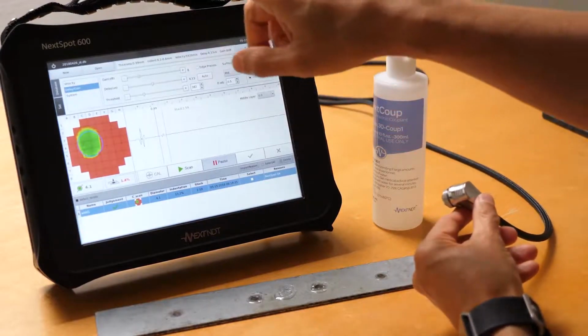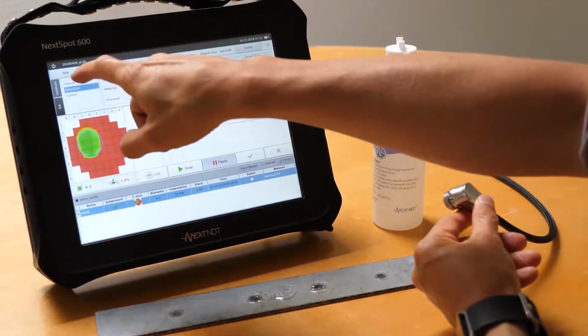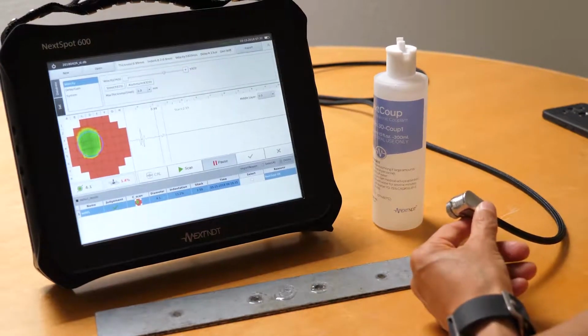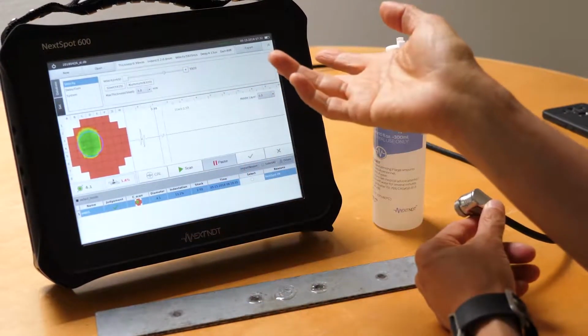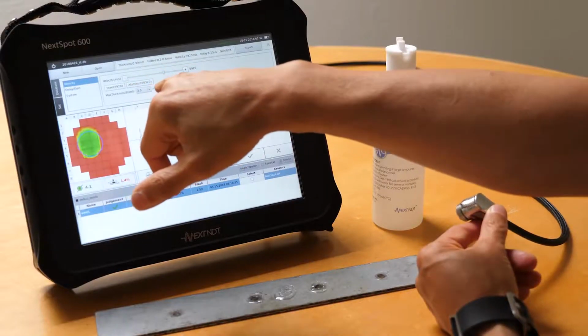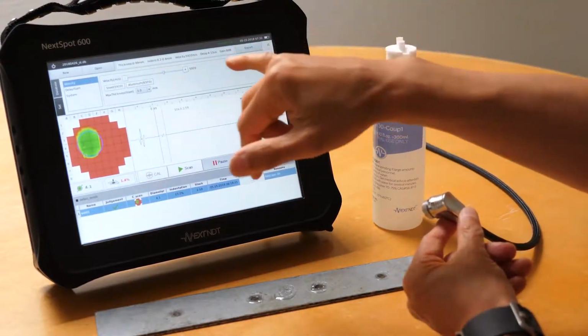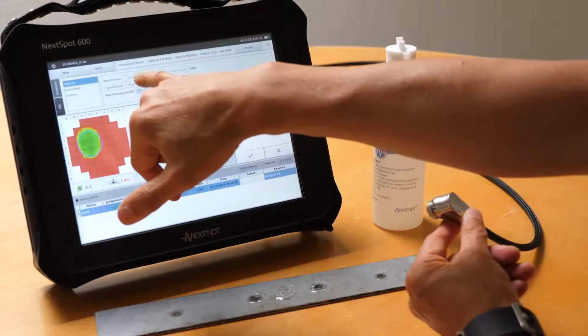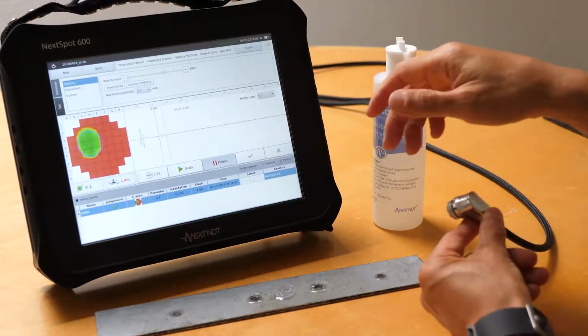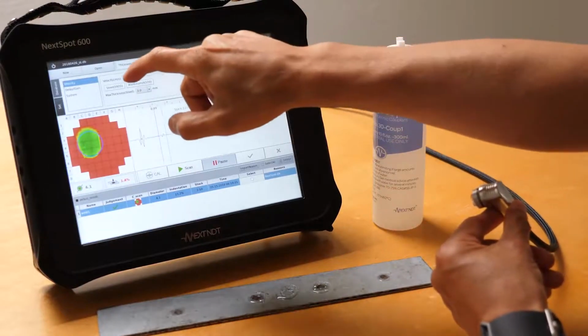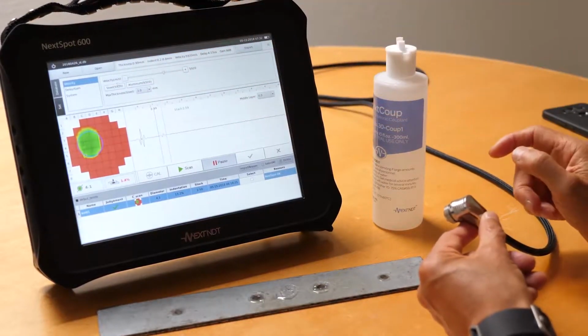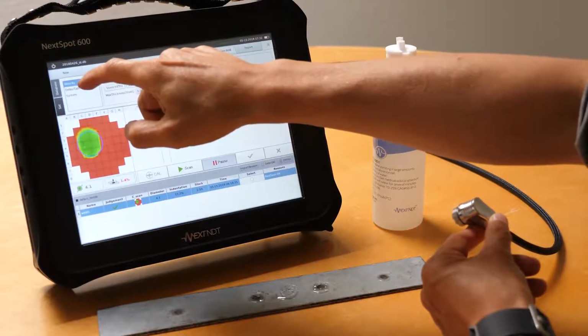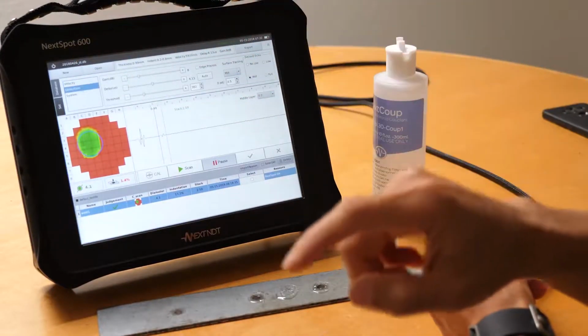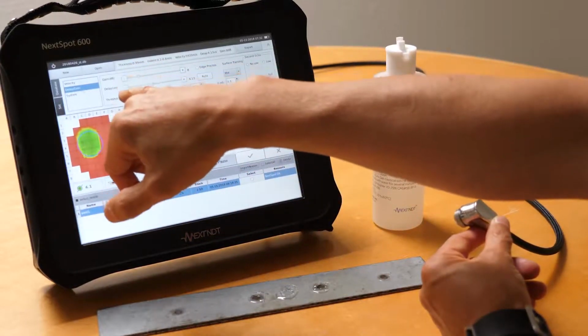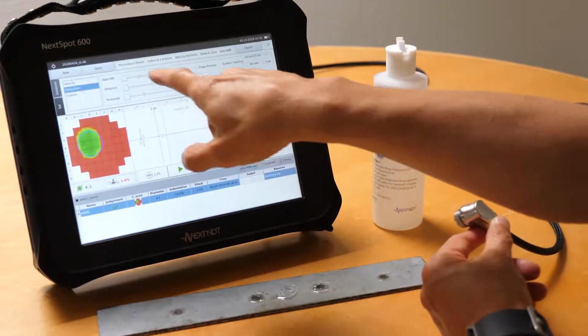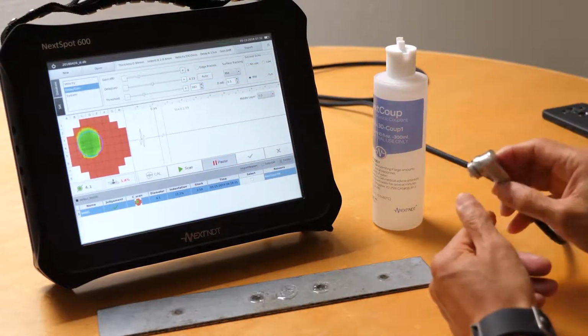The first thing I need to show you is that there's a velocity, as in all metal there are different types of velocity. You've got steel and aluminum, and if you have a different type of metal, then you can do a manual adjustment on the velocity. Since this is steel, I'm going to click steel here. And then to fine-tune this calibration even further, there are gain, delay, and threshold, which you can each customize.